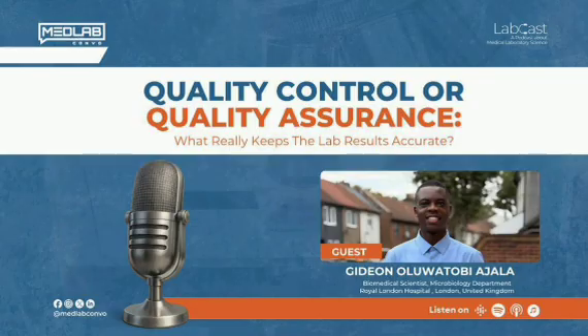You have to do your QC on the machine, and you can't compare laboratories. Probably there is another laboratory that has the same machine as the laboratory in which I work. With the same machine, they might decide to do their own quality control once in a day, based on the number of samples they process. Depending on the number of samples you process for quality control, you can design your own method, maybe once or 2 times in a day on the machine. The charting of temperature, you can make it morning and afternoon, depending on the weather or the environment where you're working.